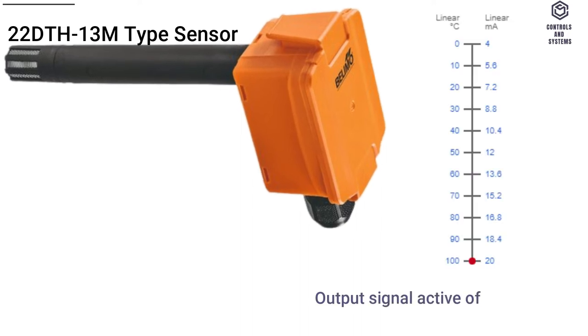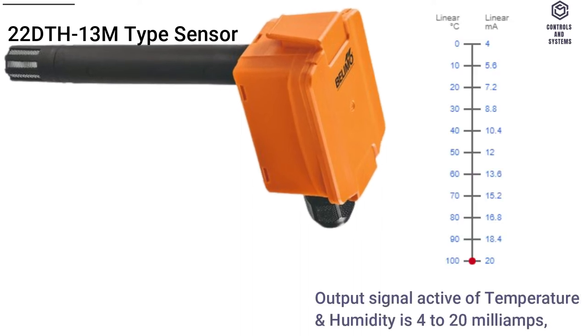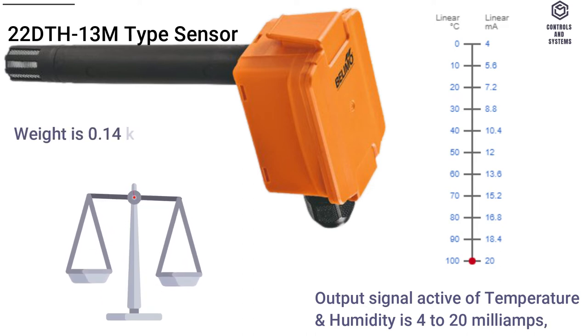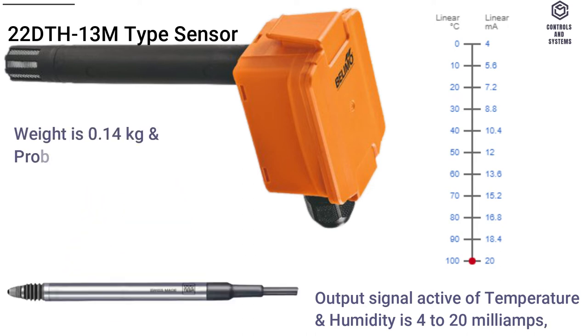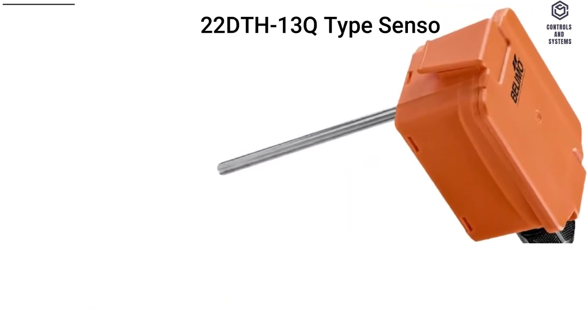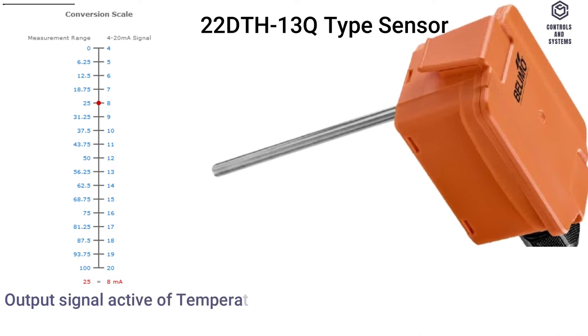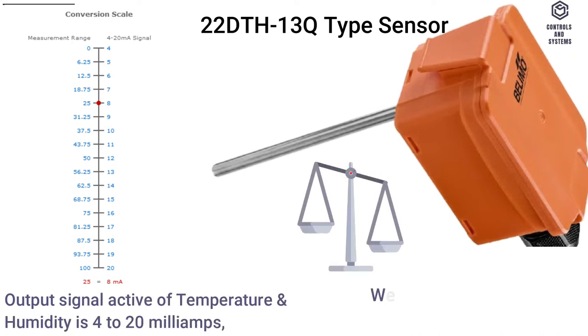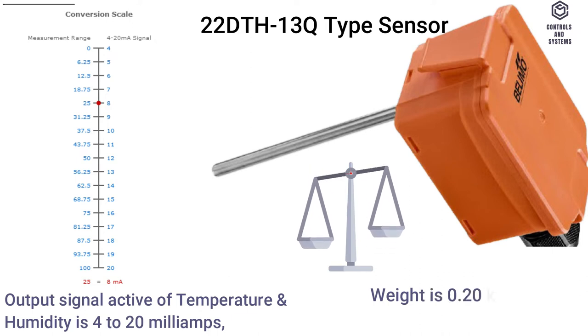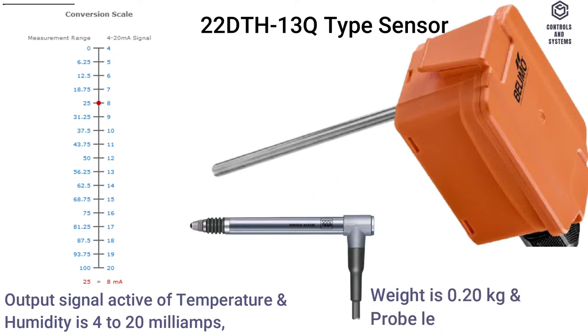22 DTH 13 M type sensor: output signal active of temperature and humidity is 4 to 20 milliamps, weight is 0.14 kilograms, and probe length is 140 millimeters. 22 DTH 13 Q type sensor: output signal active of temperature and humidity is 4 to 20 milliamps, weight is 0.20 kilograms, and probe length is 270 millimeters.